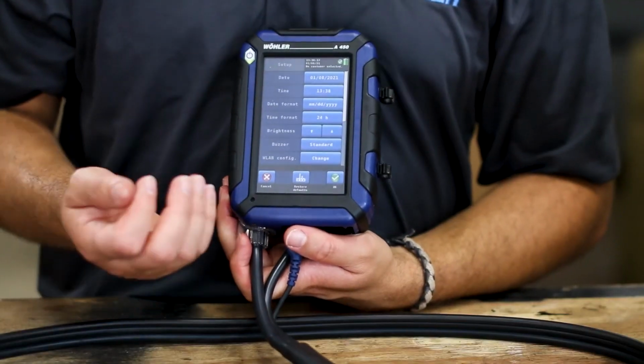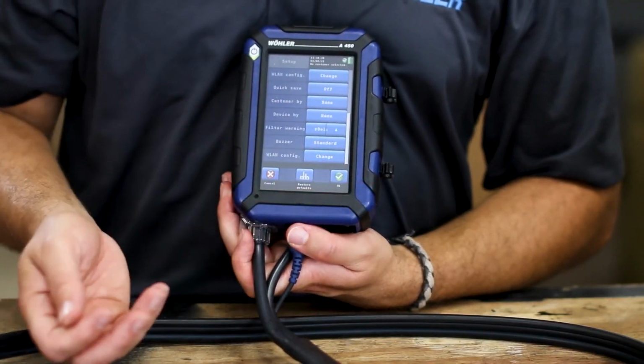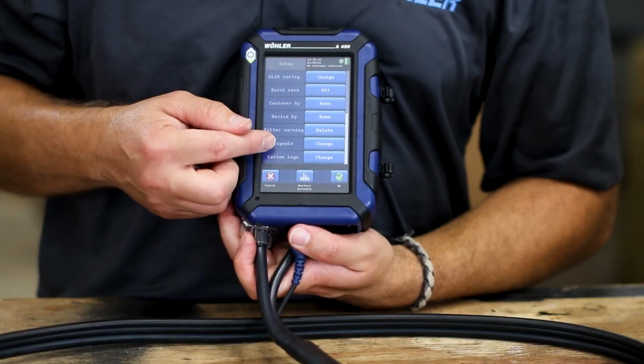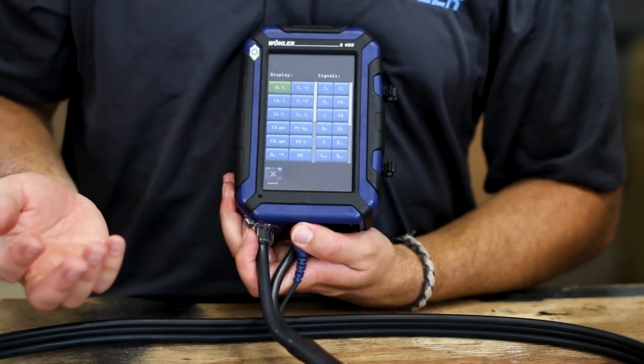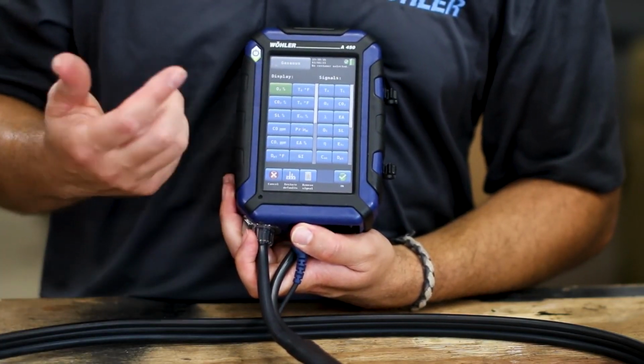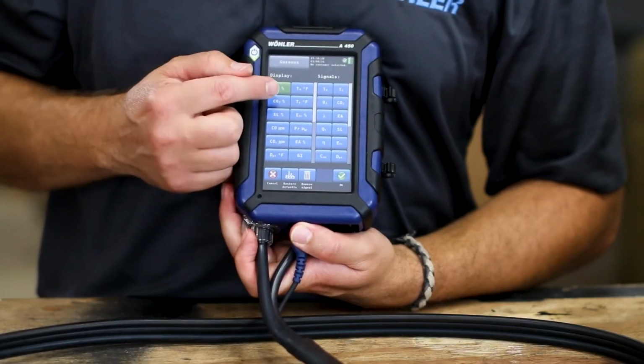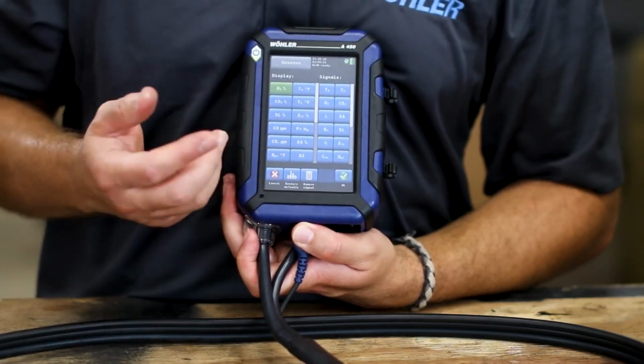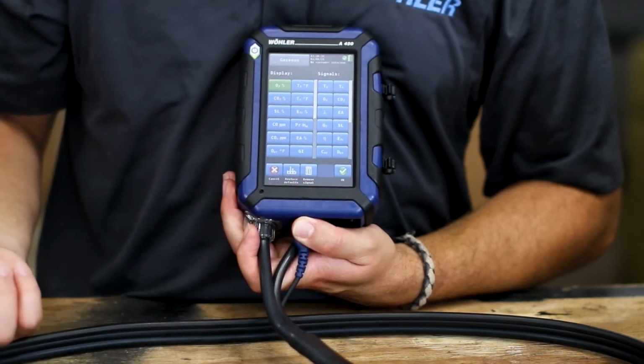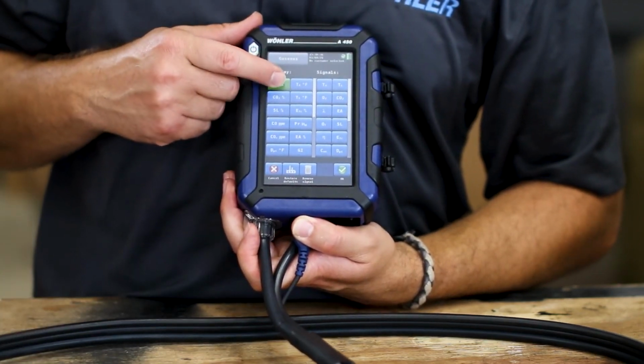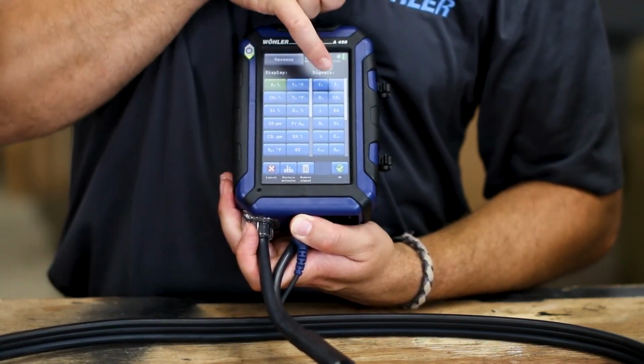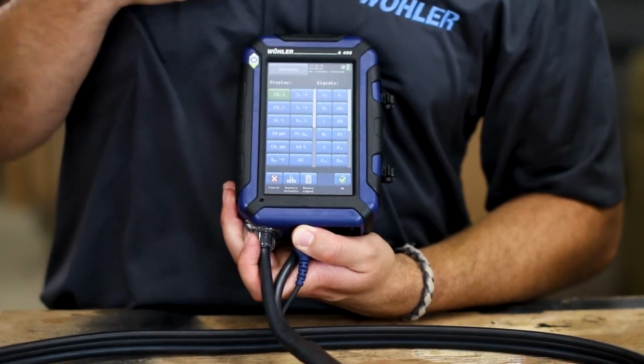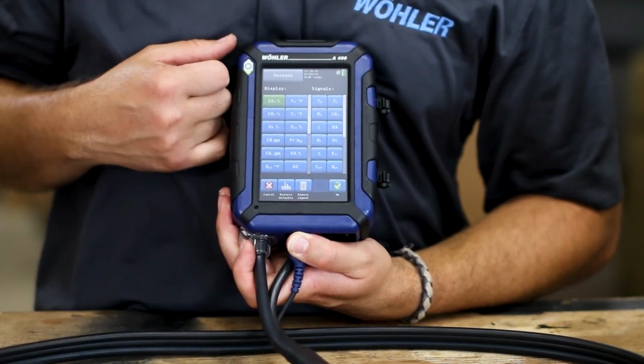If you toggle all the way to the very bottom, you'll notice in the second to lowest bar an item that says signals, with a button next to it that says change. From there, you can highlight any of your active signals that the probe is picking up and replace them with any of the signals on standby. Simply highlight that one signal and hit the signal on the right-hand side of what you want to replace it with, and it is instantly changed.